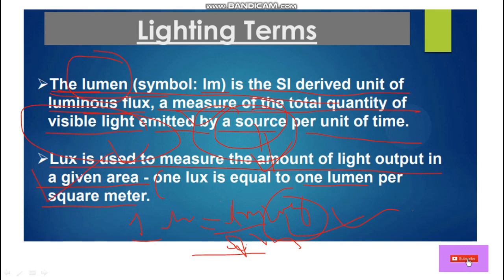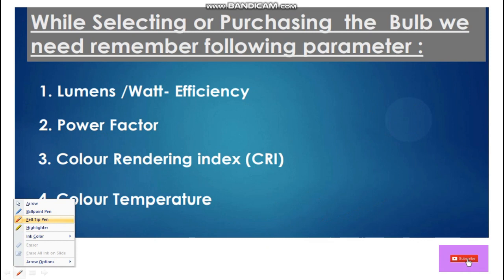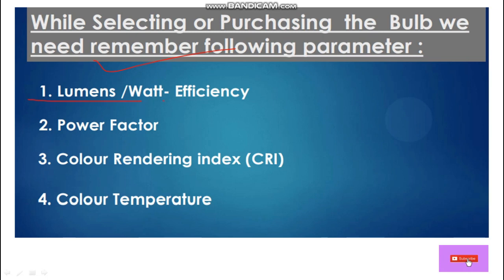We have different lux levels for different areas as per standard. When we are going to select or purchase a light fixture, we have to consider the following parameters: lumens per watt — which is the efficiency of the light fixture — then power factor level, then CRI value which is Color Rendering Index, and then color temperature.